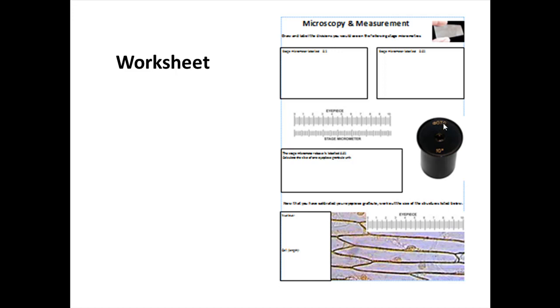When you look through a microscope in the eyepiece, you'll see a small scale, and you can use that scale to measure cells, but first you need to calibrate it. The reason for that is that scale is just an arbitrary scale — it doesn't really have any value associated with it. If you look at something under low, medium, or high power magnification and try to measure it, you'd get three different sizes, when in actual fact what you're looking at hasn't changed in size — it just appears bigger because of the magnification. So first, we need to calibrate the eyepiece under a certain magnification and establish what one unit on the eyepiece actually is worth in terms of a physical distance.